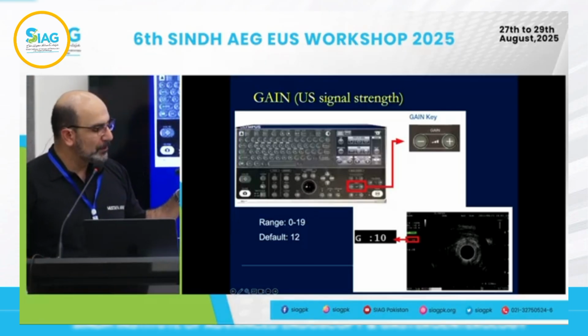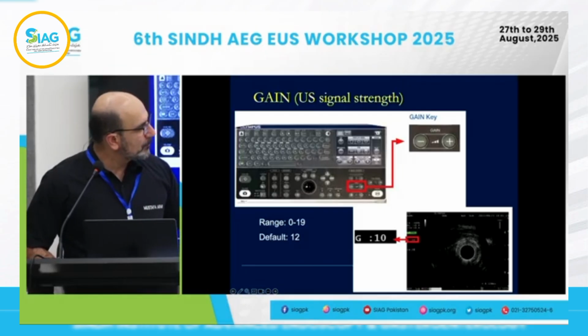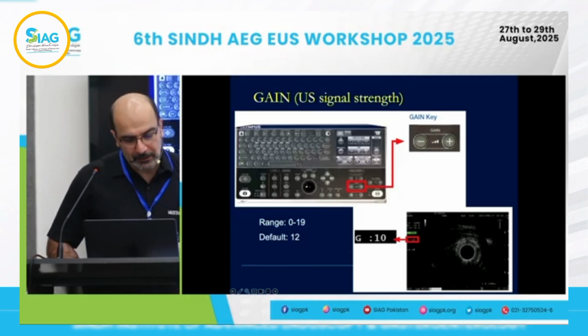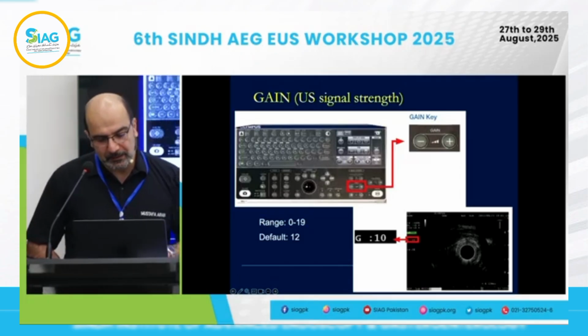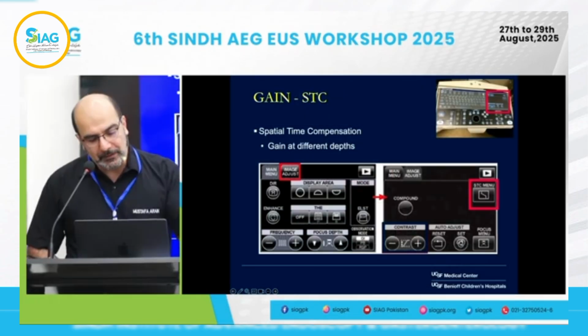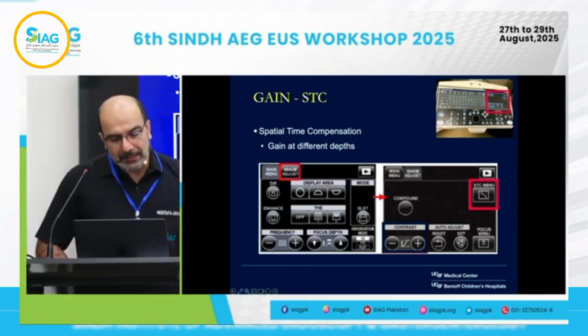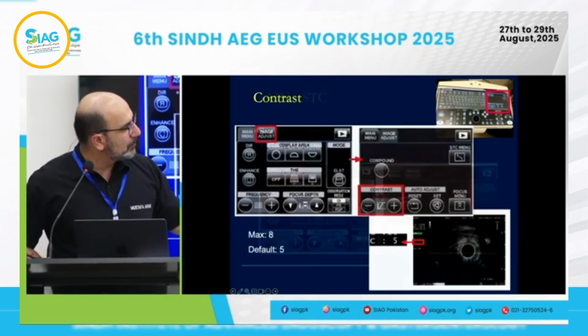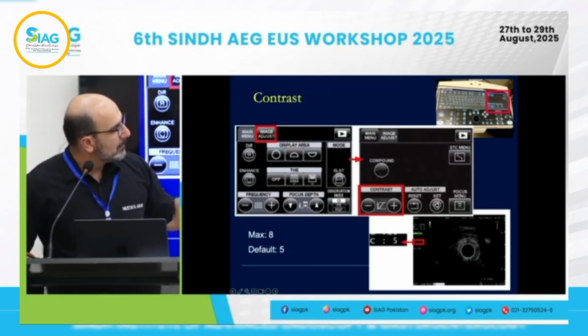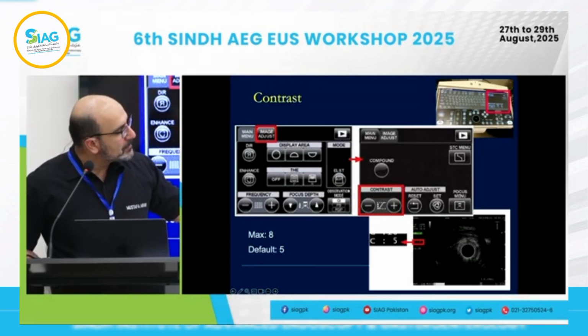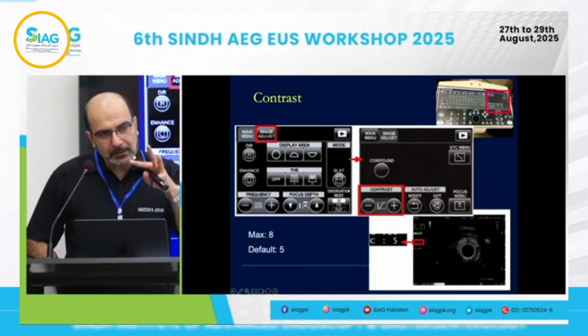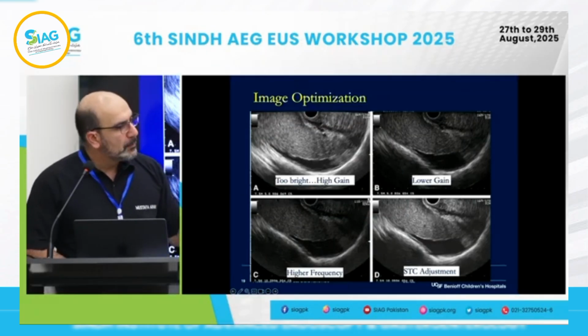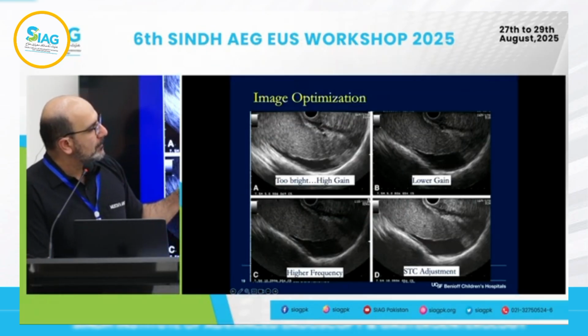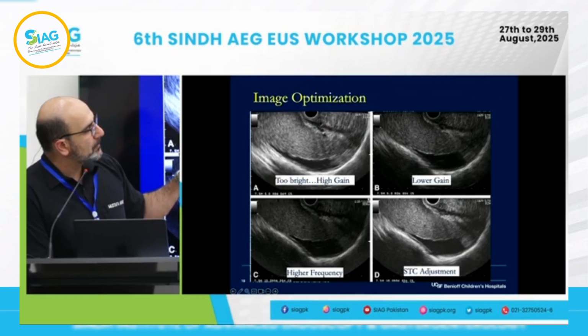But anyway, you'll see all these. Then the gain button, which is like the brightness, to increase the strength of the signal. In fact, this is me just giving you a list that you'll forget. But then the STC function, then there's a setting, and you go to that, and you can do the STC contrast, etc. So you can adjust things. It's just like photography, right? You can adjust your things to get a final good image. But some principles: too much gain will make your image too bright, which means there's too much signal that you're transmitting, and too low gain will make it too dark. So you have to find that balance.